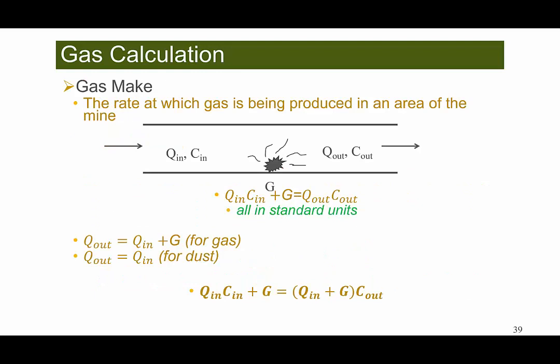Now let's look at the gas make problem. In a gas make problem, you have the total volumetric flow rate at the inlet (Q_in), the concentration of a certain gas at the inlet, and the gas make G — the rate of emission of that gas. You also have the total flow rate at the return (Q_out) and the concentration of that gas in the return air. The relationship is: Q_in × C_in + G = Q_out × C_out.